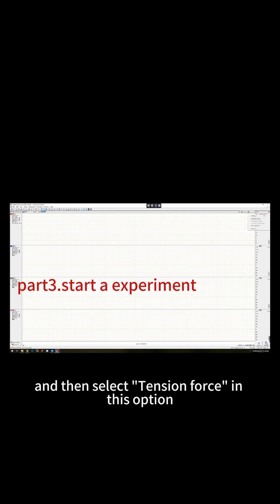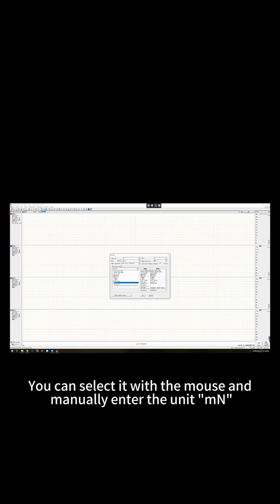Now suppose our sample is connected to the first channel. First, measure it and click Setting. If the calibration is complete, you can select Setting here, and then select Tension Force in this option. Select 30 grams for type, and General for data analysis. You can modify the unit here. Currently, mN is used. You can modify it to gram or kilogram. If there is no mN in the drop-down option, you can select it with the mouse and manually enter the unit mN. Click OK to start the experiment. At this time, the setting is modified.